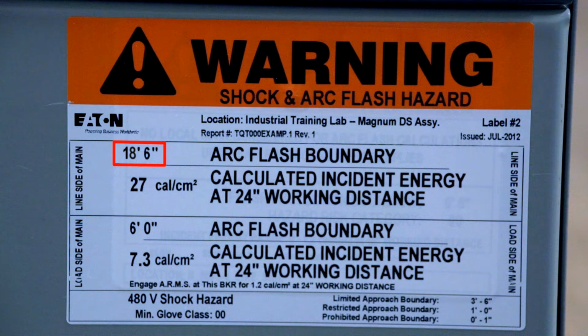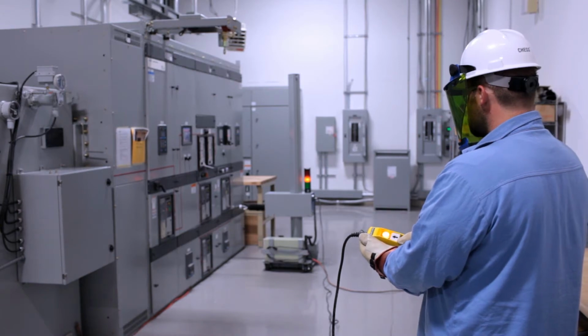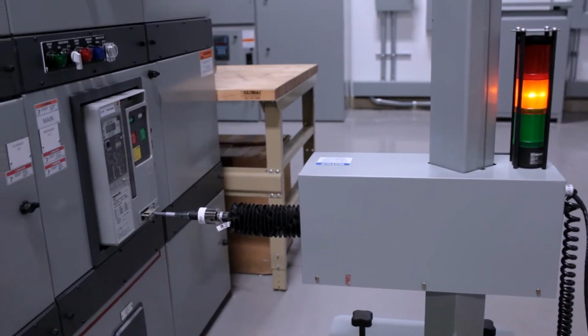The second critical piece of information on this label is distance. This label shows that in order to avoid a second-degree burn, a person without arc flash personal protective equipment, or PPE, would have to be 18.5 feet away. The only way to operate on equipment from this distance without PPE is to do so with some type of remote control device or equipment.